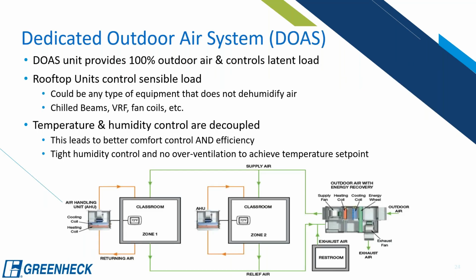So what does that look like in a system? This diagram here does a good job of representing it, but the DOAS unit provides 100% outside air and controls the latent load. The rooftop units control the sensible load. And that rooftop unit, by the way, could be any type of equipment that does not dehumidify the air, or in other words, is kind of like a sensible equipment. So that could be chilled beams, VRF, fan coils, radiant panels, baseboard heat, anything like that. What this means is that the temperature and humidity control are decoupled. So this leads to better comfort and efficiency. The tight humidity control, and you don't overventilate the space, which just provides better efficiency.